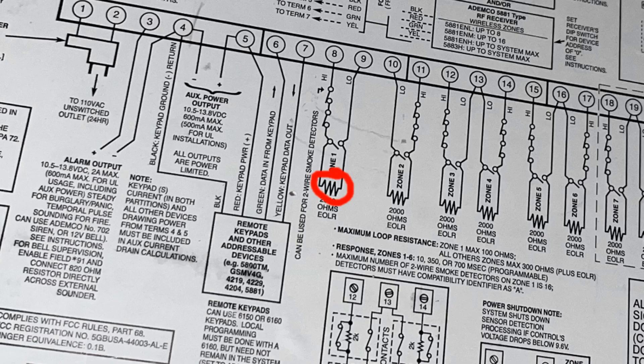So you can actually use resistors for every zone if you wanted to, if they were normally open zones. But if they're normally closed, yeah, there's really no need for that because, I mean, what the resistor is really doing for you is supervising the zone.